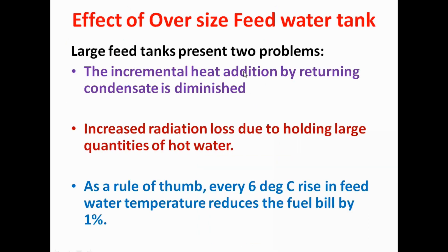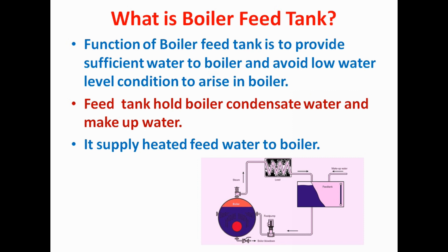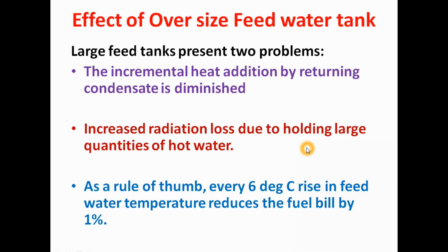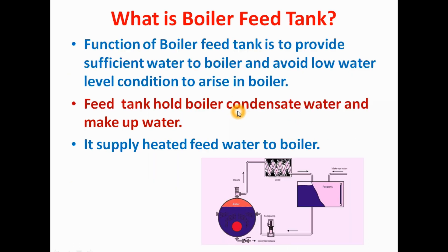Now we will see the effect of an oversized feed water tank. If the feed water tank is oversized beyond the required size, the incremental heat addition from returning condensate is diminished. There will be heat loss and radiation losses, which will reduce the feed water temperature. Due to the reduced temperature of the feed water, boiler efficiency gets reduced.